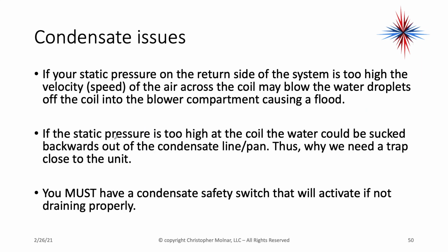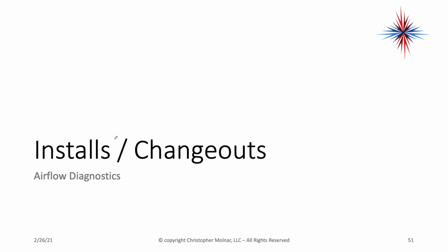If your static pressure on the return side of the system is too high, the velocity of the air across the coil could blow the water droplets off the coil into the blower compartment, causing a flood. If the static pressure is too high at the coil, the water can be sucked backwards out of the condensate line or pan, thus why we need a trap close to the unit. Note, you should have a condensate safety switch that will activate if the system is not draining properly. You don't want to cause a flood.